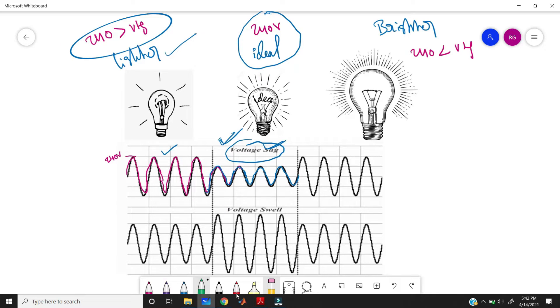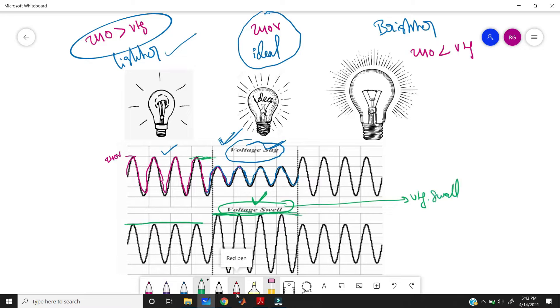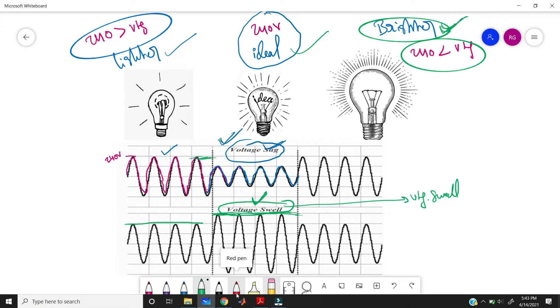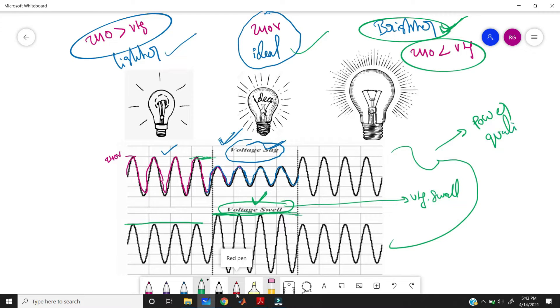We also have another effect that is totally opposite to voltage sag, known as voltage swell. In voltage sag you get less than the normal voltage, but in voltage swell, if you supply constant voltage, at some point in time you get more than the rated voltage — higher than the rated voltage. In that condition, the bulb will be supplied greater than the rated voltage and will glow brighter than normal. These two effects also affect power quality.